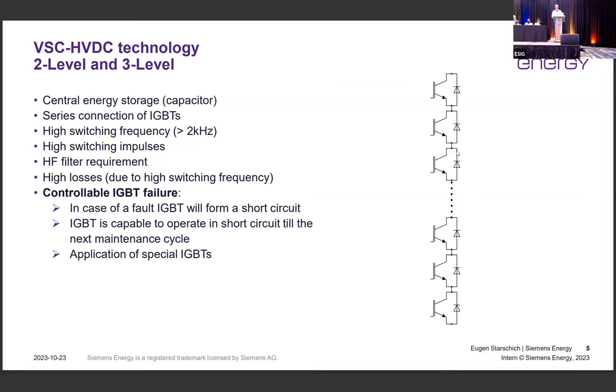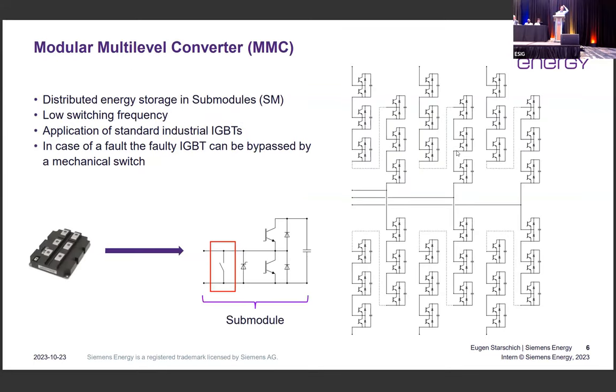So the key features of this two and three level technology were very high switching frequency, more than 2 kilohertz, high switching impulses, high frequency filters, high losses, and the series connection of the IGBTs. And we were talking before about misunderstanding about the VSC HVDC technology. Many of these misunderstandings come directly from this time, from the 90s, where we had two or three level converter technologies. So the change was made with the introduction of the modular multi-level converter, or MMC.